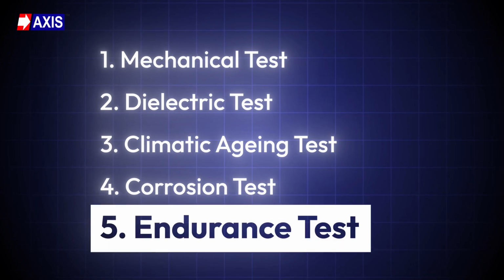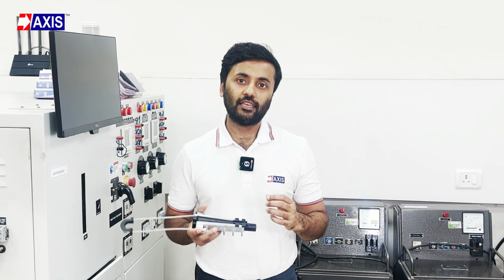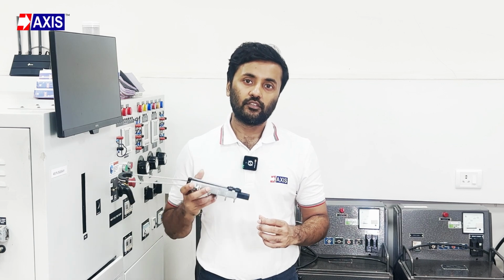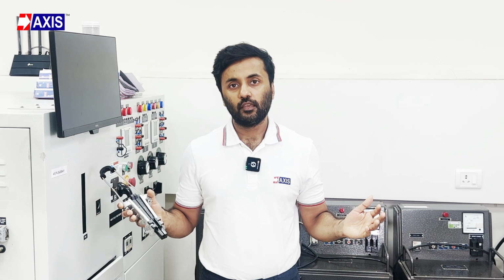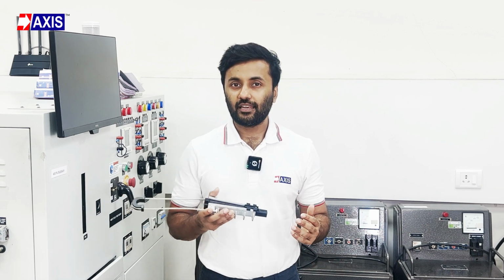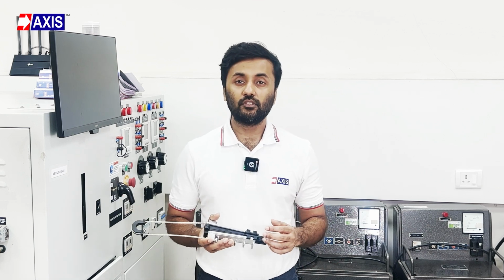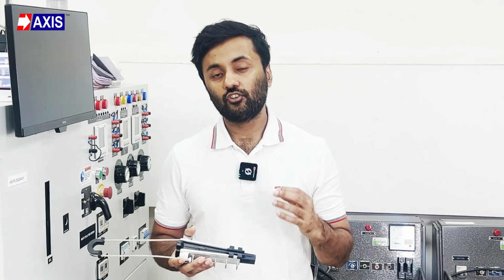The endurance test. The goal of this test is to confirm that the anchoring clamp can withstand repeated temperature changes and mechanical load without failing over time. How do you conduct this test? First, you fit the clamp onto both ends of an insulated neutral messenger cable, keeping a 2-meter distance between them. Place the setup in a test loop that runs 500 cycles. Each cycle lasts 90 minutes. Apply 10% of the minimum breaking load as mechanical tension and mark the cable to observe any slippage. Follow this for each cycle.